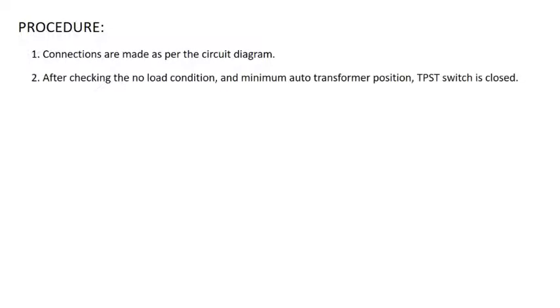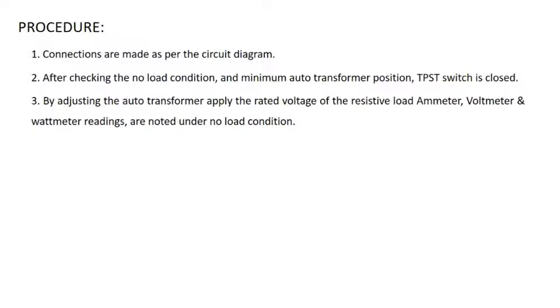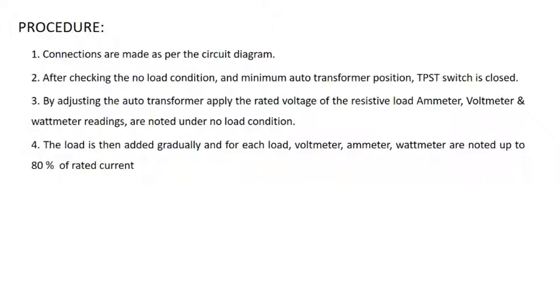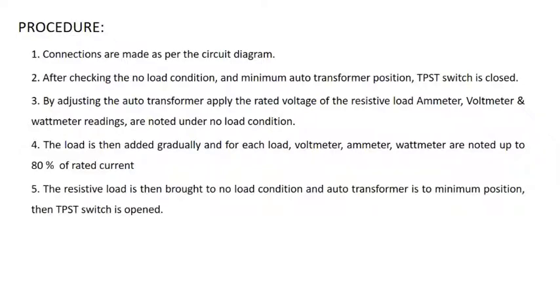Now the procedure. First, you need to give the connection as per the circuit diagram which you will see in the next slide, and check that no load is connected, with all the resistance loads in off condition and the auto transformer in the minimum position. By varying the auto transformer, you apply the rated voltage to the resistance load. The load is gradually increased from no load to 80% of the rated current, and you note down the different values of voltage, current and wattmeters. Lastly, the resistance load is brought back to the no load condition, the auto transformer is moved to the minimum position, and the TPST switch is opened.